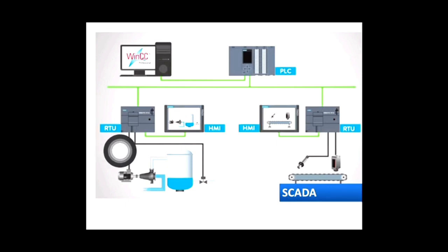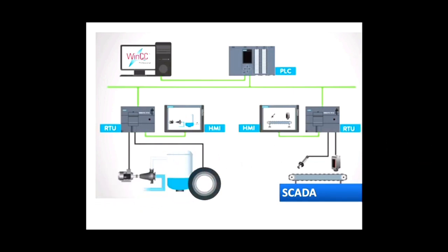This is a remote terminal unit — it's a microprocessor-based device used to control and monitor the field devices, such as the pump and water tank. RTU is somewhat like a PLC, but it is more expensive compared to PLC, though its environmental tolerance is higher than PLC.